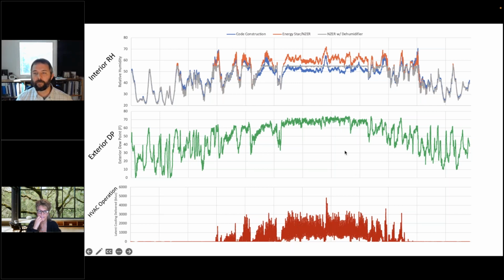The reason I added these bottom two graphs is to show why we have this consistent cycling of relative humidity in the summer. It's because we have high exterior dew points, high heat, and good cycling of AC with long runtime. So we have higher moisture, but we're balancing that out with higher removal rates.